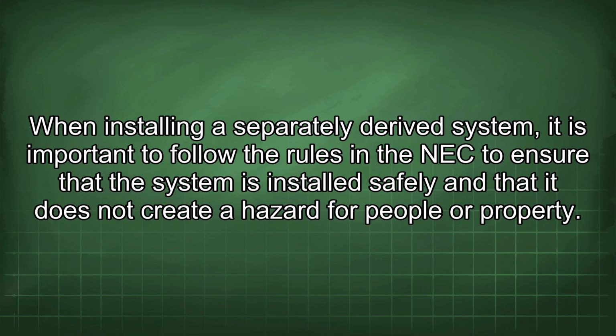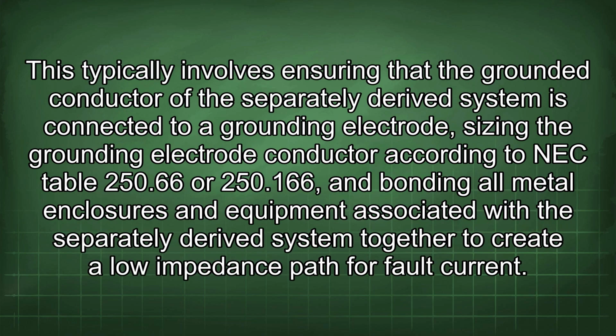When installing a separately derived system, it is important to follow the rules in the NEC to ensure that the system is installed safely and that it does not create a hazard for people or property. This typically involves ensuring that the grounded conductor of the separately derived system is connected to a grounding electrode, sizing the grounding electrode conductor according to NEC table 250.66 or 250.166, and bonding all metal enclosures and equipment associated with the separately derived system together to create a low impedance path for fault current.